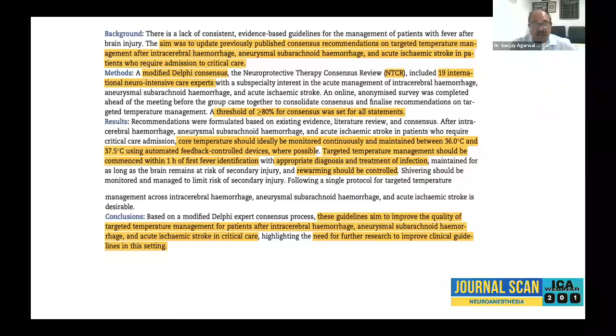Core body temperature was the most useful surrogate measure for brain temperature, with a level of consensus of approximately 90%. An automated device for targeted temperature management is indicated for high quality temperature control for treatment of neurogenic fever in adult patients. 100% consensus was there. Targeted temperature management should be used reactively, using an automated device to maintain normothermia. The target temperature to be maintained was between 36 and 37.5 degrees. Again, 100% consensus was there.